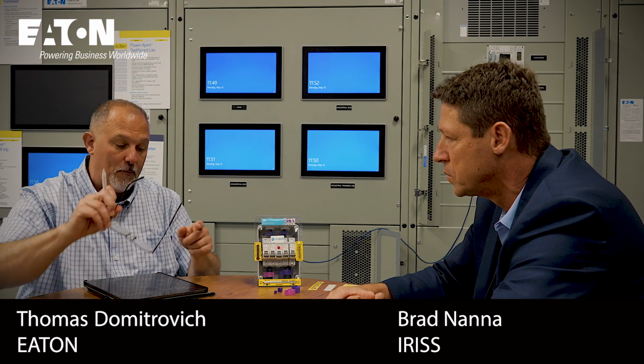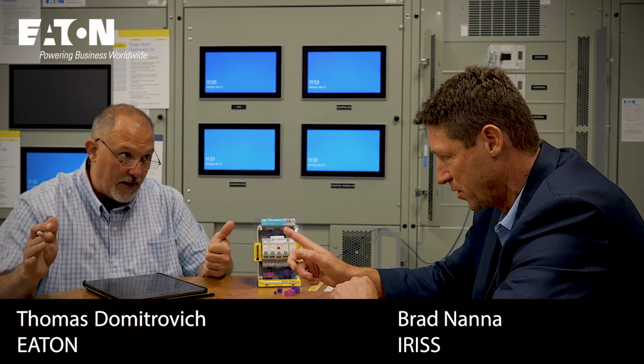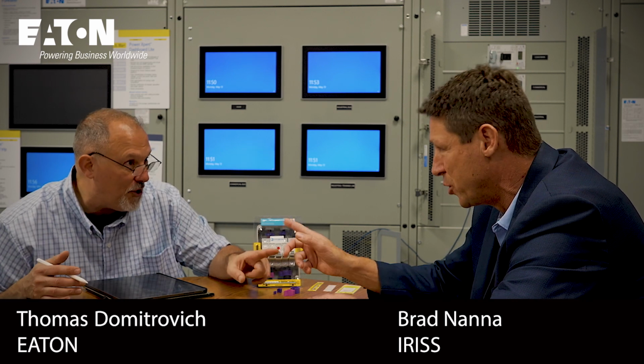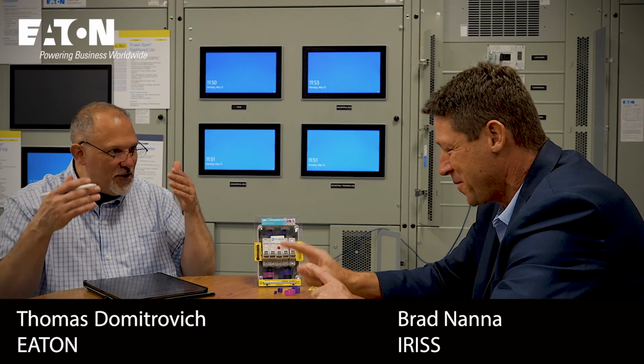Now, 70E and 70B—70B has section 7.4, which I want to revisit. 7.4.2 talks about removal of covers, and 7.4.1 says infrared thermography shall be used when required to verify temperature differences of similar electrical components under similar loading, and comparisons between electrical components and ambient air temperatures. That's your point—changing the ambient as soon as you take the panel off. So how would you even do that comparison? You can't.